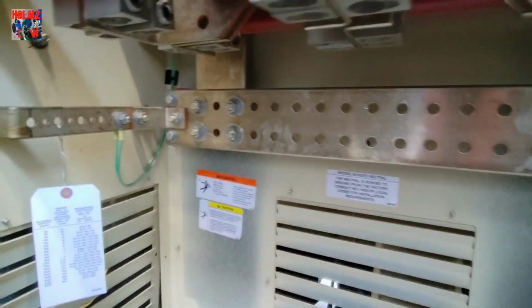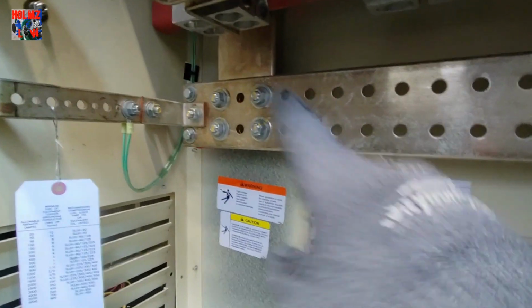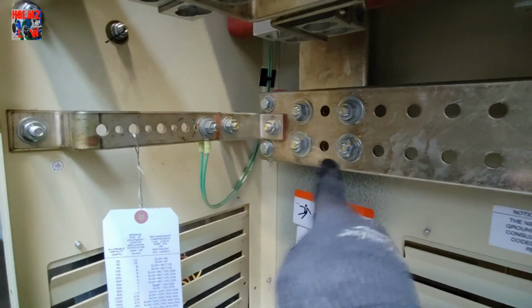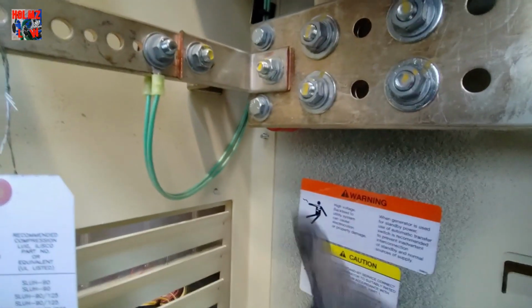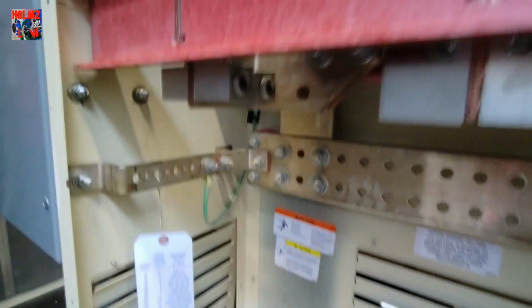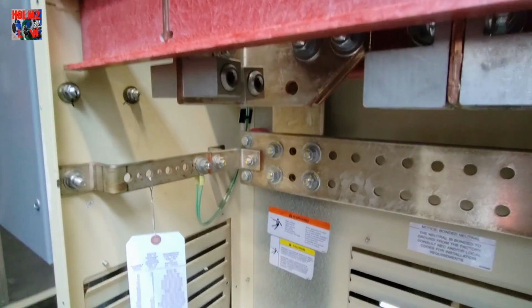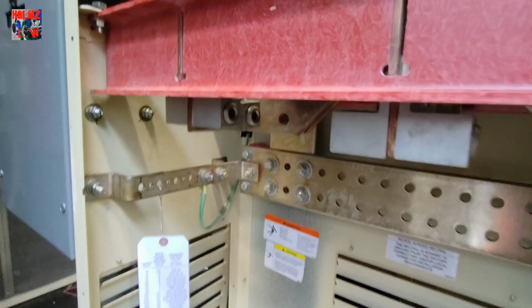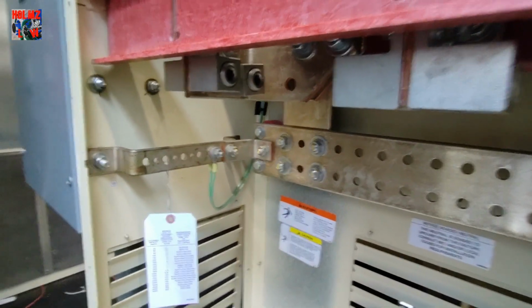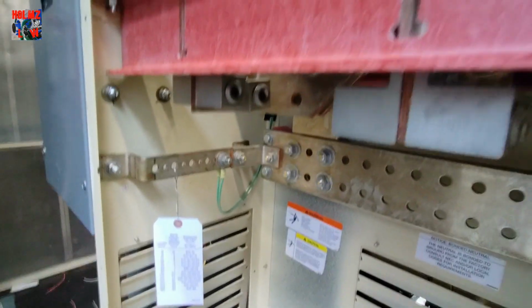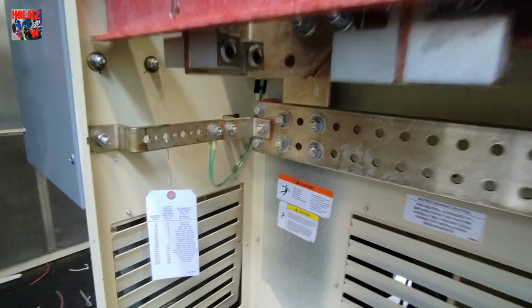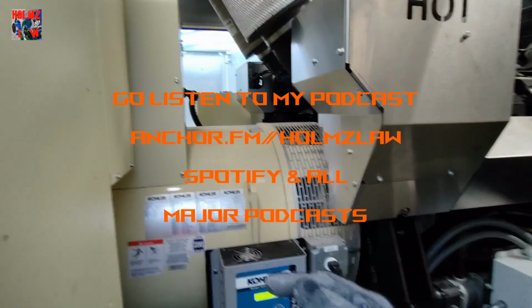So if we look under here, we see that this is the neutral bar. This is the neutral bar, and this is my ground bar, and it's being bonded. That's the system bonding jumper there. So that's actually what's making this a separately derived system. In order for us to actually have this be a separately derived system, we have to also use a specific transfer switch. Now, what type of transfer switch? I'm going to show you what type of transfer switch we're going to need to use.